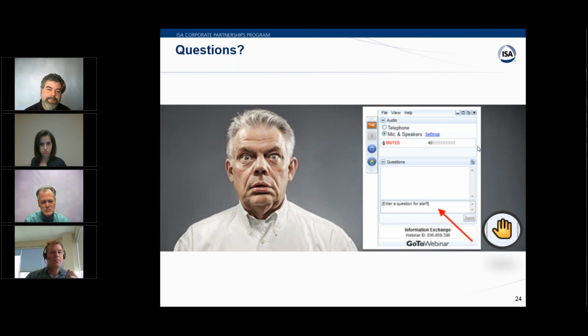Some have a brush. You can get a very soft brush that could be used rather than a wipe, just like you have different toothbrushes. I'm one of these guys that has sensitive teeth, so I use the fine or extra fine toothbrush. They have brushes as well to clean pH probes if it's really scummy stuff that you're having to get off there. But non-contact ultrasonic would be the first choice. Otherwise, I'd look at these brushes that the manufacturers tend to provide.